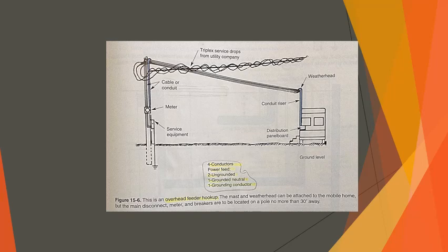An overhead installation consisting of a mast and a weatherhead. This type is for permanent installations or where the load exceeds 50 amps. See Figure 15-6.